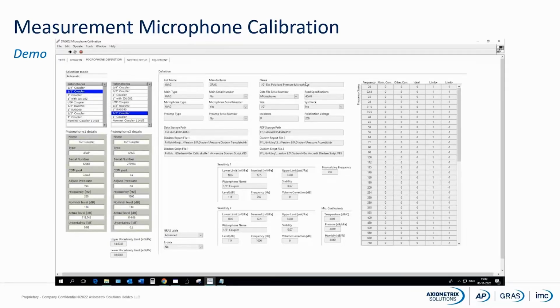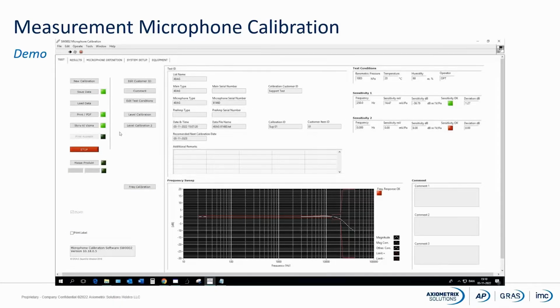Also polarization voltage. We can also see where we actually store the data, where we store raw data, where we store the certificate, where we get the templates for the certificate. We do also have data for the sensitivity tolerances, upper and lower tolerances, both for sensitivity 1 and 2, and the same for our frequency sweep. And under equipment, we can actually see the list of equipment we have used for doing this calibration. Okay, it was about the microphone calibration system.